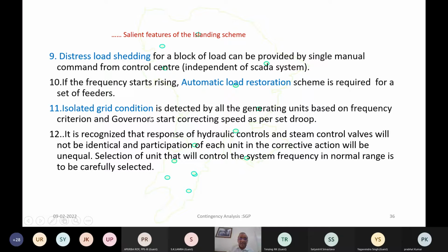Now, isolated grid condition by breaker input will perhaps not be possible locally, because you are still interconnected with the grid, and as far as the powerhouse is concerned, the governor will see as if it is connected to the interconnected grid, but actually you are operating in isolated mode. So there are islanding detection modules available, based on the vector change or on frequency criteria, etc. And they need to initiate the supplementary controls to keep the frequency under control.